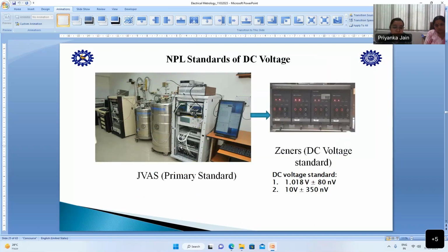So this is the NPL standard of DC voltage. On the left side, you see this steel one is the helium container, and our Josephson array is placed inside this. Here you can see a small wire. We are giving the frequency using the frequency generator, and other outputs are connected here. That means we are connecting our Zeners. These are all the Zeners. These Zeners are calibrated against our Josephson array, and we compare Zener voltage with the Josephson array voltage using a nanovolt meter here.